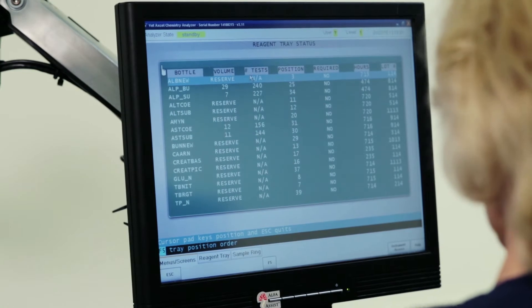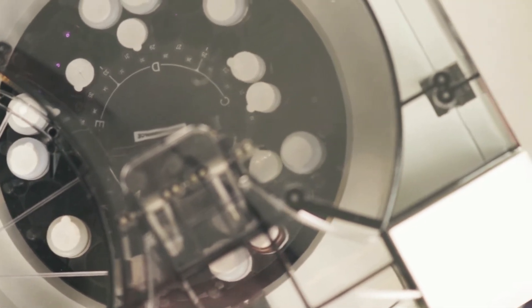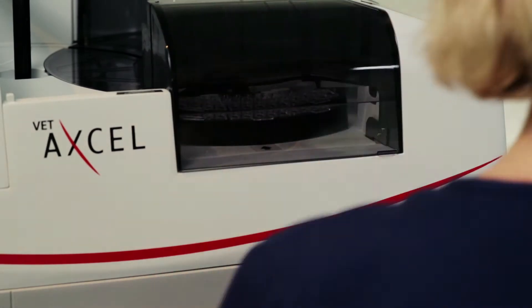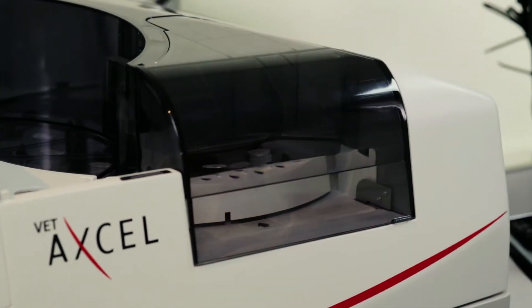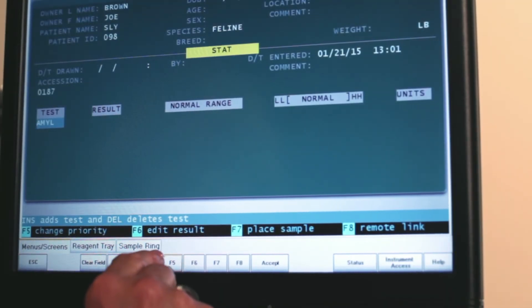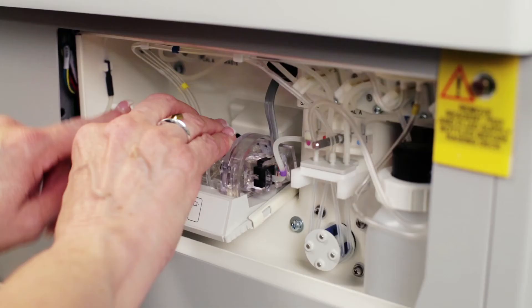The VetAxcel can measure up to 40 different assays on board at one time. Once placed on the instrument, on-board refrigeration ensures longer reagent stability, less maintenance time, and an easier setup. The VetAxcel allows the user to run tests in any combination, individually or in custom-made panels. Any test or panel can be run STAT at the touch of a button. Electrolytes are directly measured by ion-selective electrodes that are easily maintained.